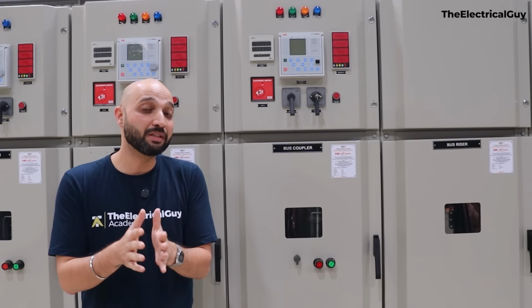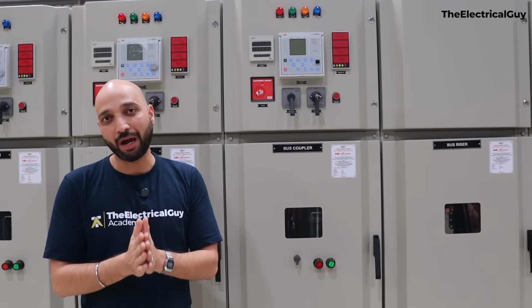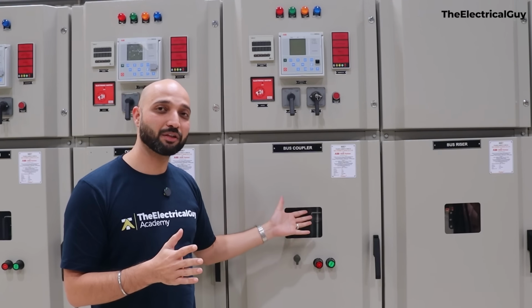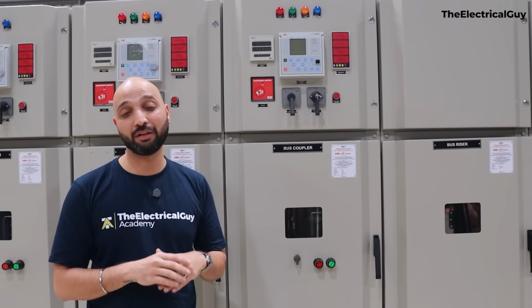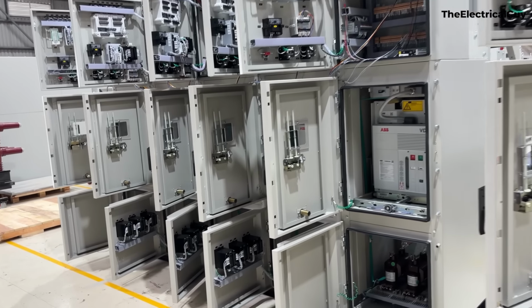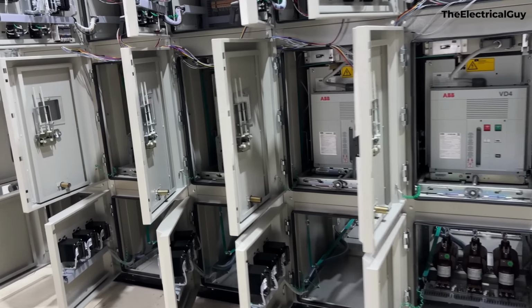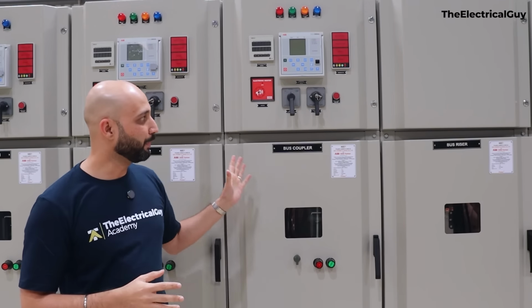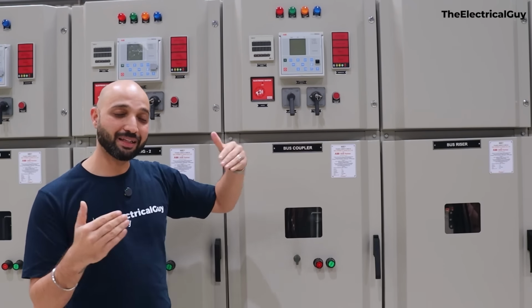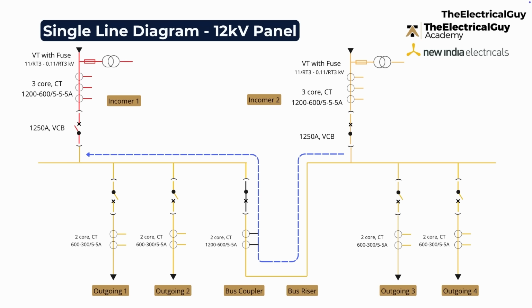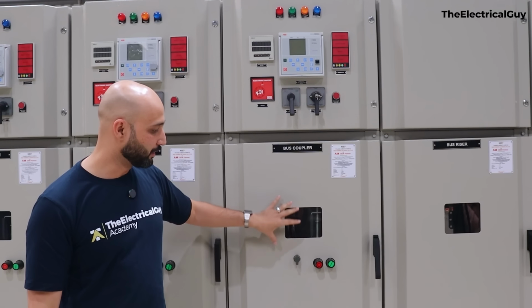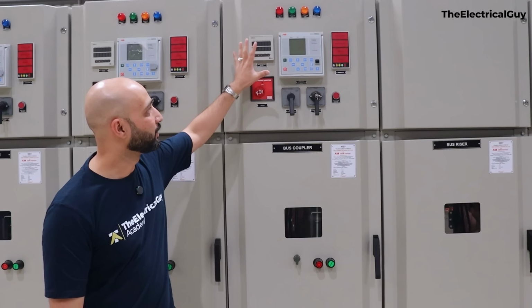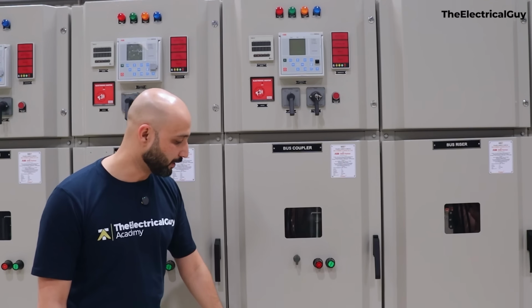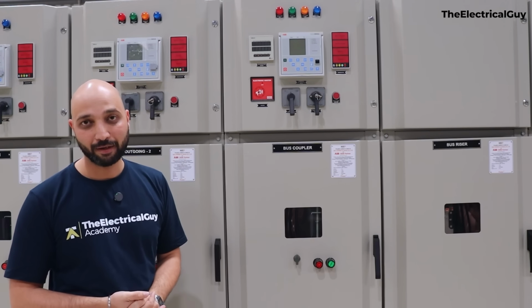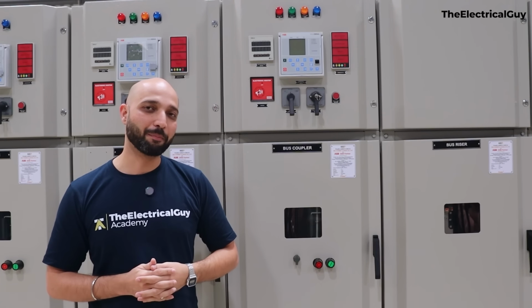Now, the question is, do we always need it? Maybe not. If you have multiple supplies, it makes a good choice to have the bus coupler. But if you have only one supply, there is no use of a bus coupler in that case. So to have the supply redundancy, to have the supply reliability, we must have the bus coupler. And it's simply a series connection of two bus bars. In that series connection, we are putting a circuit breaker so that it doesn't create a short. And this is the circuit breaker that you can see. The rest is the same. We have an indication panel, and there won't be any VTs here. So that is the function of the bus coupler panel.